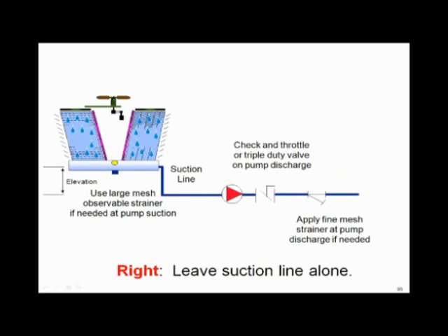If you want the little rules of thumb again, leave the suction lines alone, please. Keep the pressure drop between the suction of the pump and the tower, five feet or under. Please keep it clean. If you've got any valve, you can put it on the discharge side of the pump.